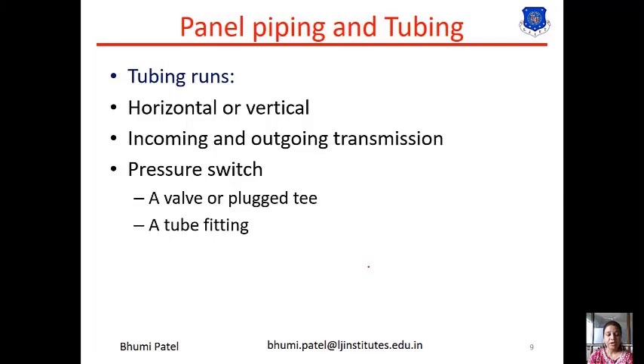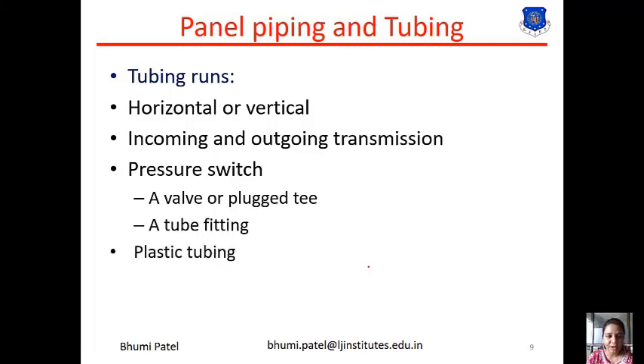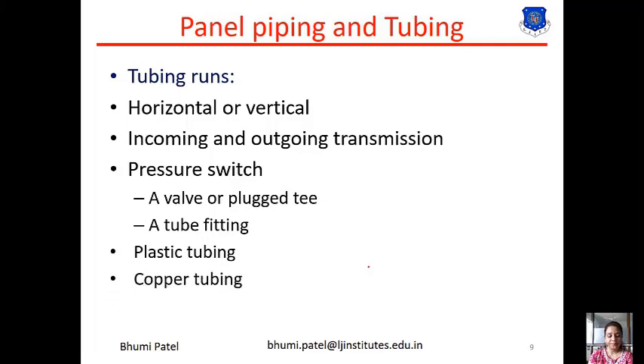This is the pressure switch requirement for the tubing run. Now there are three types of material used for the tubing run. First one is the plastic tubing. Plastic tubing has been increasingly used for pneumatic installation because it reduces labor cost compared to metal tubing. Next one is the copper tubing. Copper tubing is good for tube bending but its cost is more compared to plastic tubing.